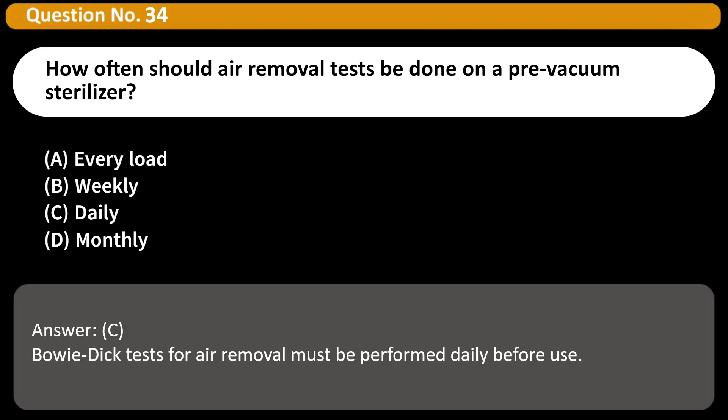How often should air removal tests be done on a pre-vacuum sterilizer? A. Every load, B. Weekly, C. Daily, D. Monthly. Answer C. Bowie-Dick tests for air removal must be performed daily before use.